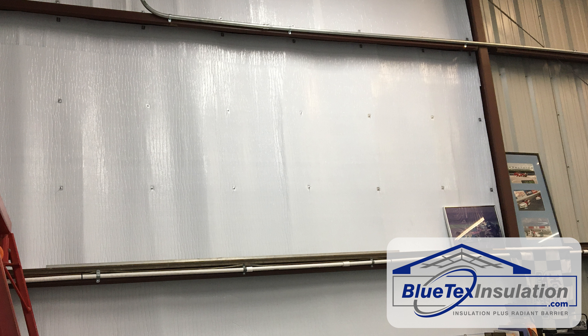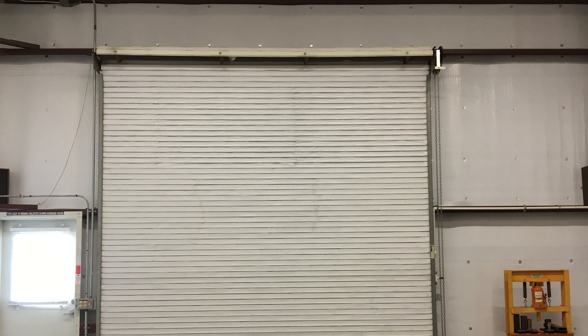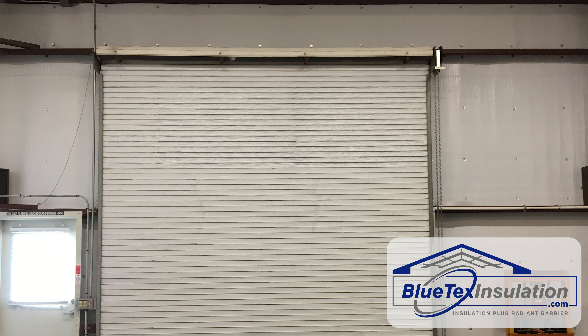The seams are sealed with the BlueTex 3-inch vapor barrier tape. To create an internal vapor barrier, your goal is to make it pretty airtight. This method will usually prevent condensation inside the building, since now the warm, moist air can only get to the inside of the BlueTex insulation and not to the cold metal.